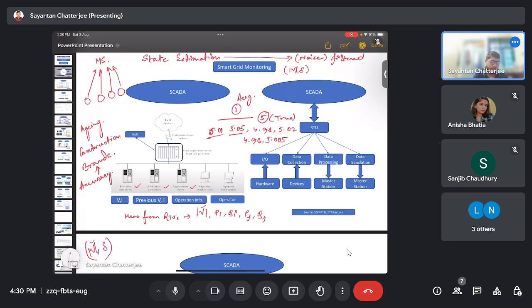When the data is received from the RTUs to the substation, the same condition applies when we need to perform a remote operation, like opening or closing a breaker. That information is given in the master station, the human machine interface, and based on that a remote operation is performed in the RTUs. These input-output ports take the information as well as deliver it to the hardware in operation, in the field, in the bay, anything. Data collection and data processing need to be done before being stored in the master station, and this is the main working idea of the RTUs.